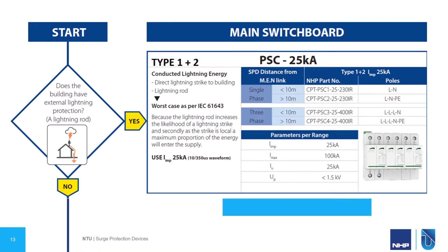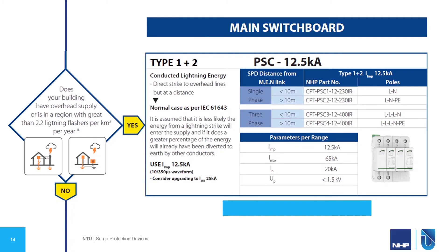If your building does not have external lightning protection, the next question is: does the building have overhead supply, or is it in a region with greater than 2.2 lightning flashes per square kilometer per year? These stats can be looked up on the Bureau of Meteorology website. If this is the case, then any lightning strike is likely to be at a greater distance, therefore less energy will be entering your installation. In this case, we can use a surge protection device with an impulse current of 12.5 kA — here, NHP has the PSC 12.5 kA. Part numbers are selected depending on whether it's three-phase or single-phase and that distance from the MEN link.